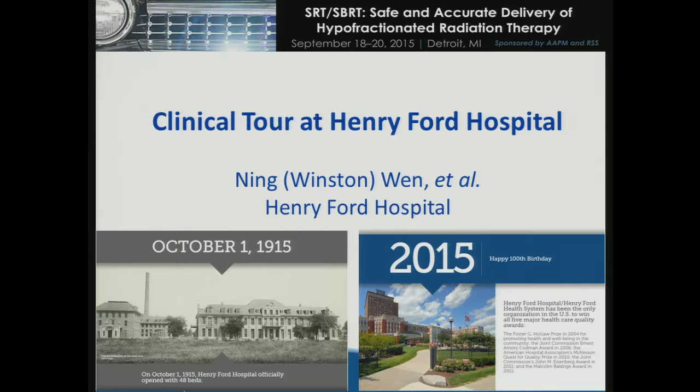Steve? Well, Sonia and Indrun, thank you both for an excellent presentation. Sonia, your request that all three modalities be the same is coming. By November, Elekta will release the cone beam CT addition to the Gamma Knife Perfexion. It's already up and running in Europe. It will include plastic face mask, will include infrared positioning system. So it's going to become much more like Linac and CyberKnife than it ever has been before. So we are all coming together. Slowly but surely.